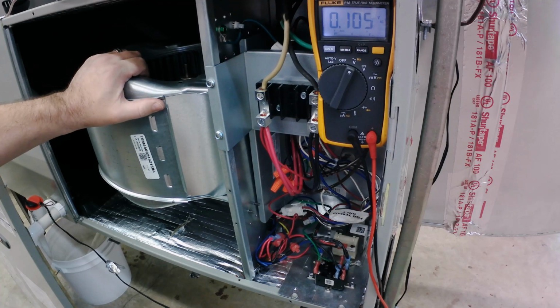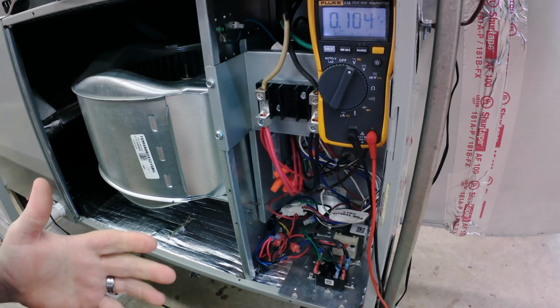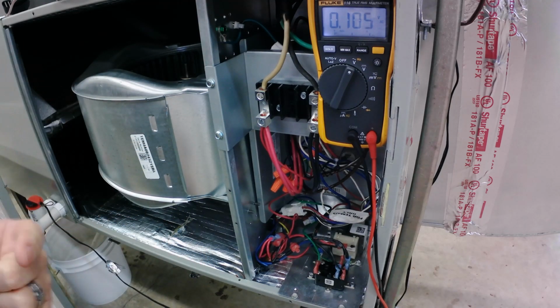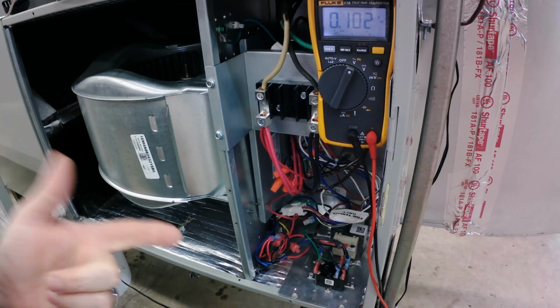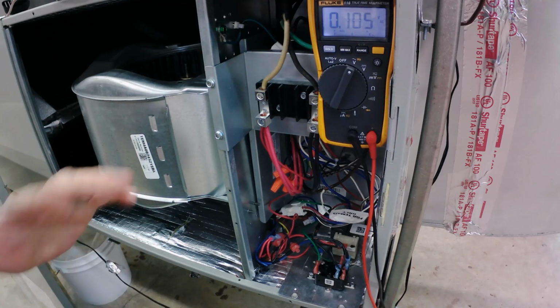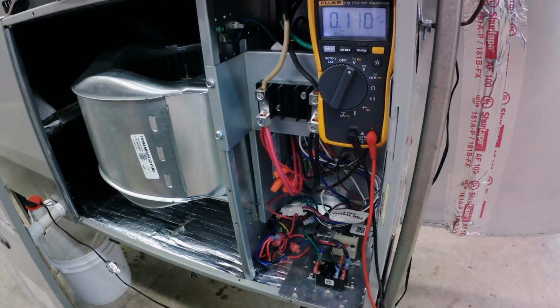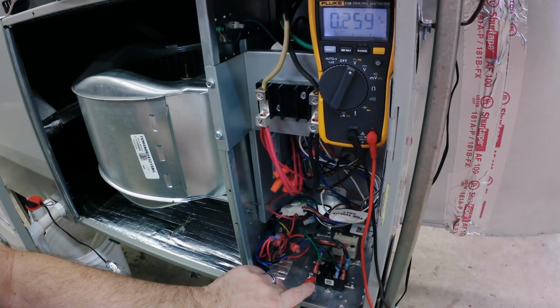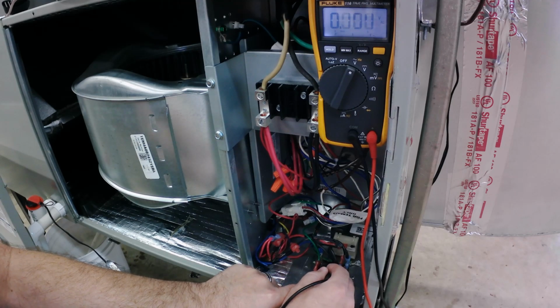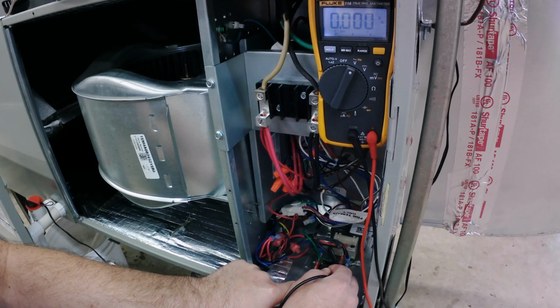So this fan motor is not working, and the first thing you need to understand is the sequence of operation is that the thermostat calls for the fan to work. Okay, so if the thermostat was doing its job, and I'm not going to bore you to death with continuity checks and stuff like that. I mean, you know they're coming, depending on the problem that you've got. But if my fan's not working, the first step I would do, since you've got the cover off the air handler, is take your meter and go from the G terminal on the relay to the common, and I've got 0 volts. All right.